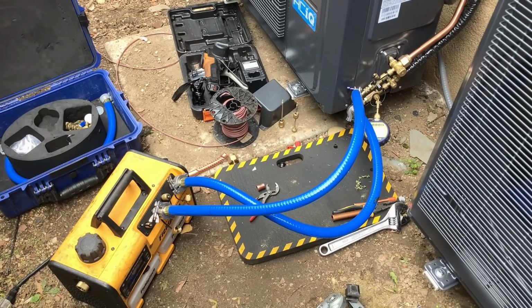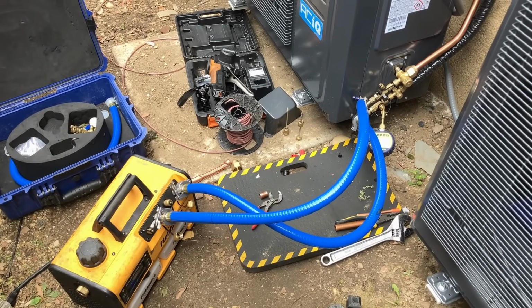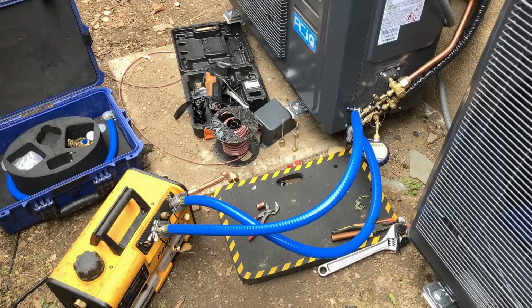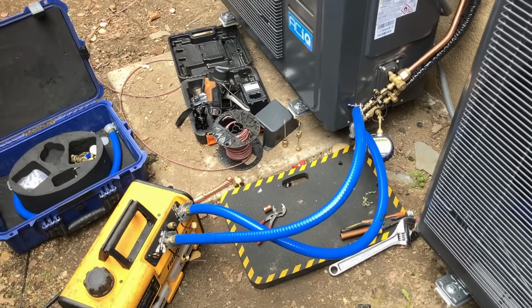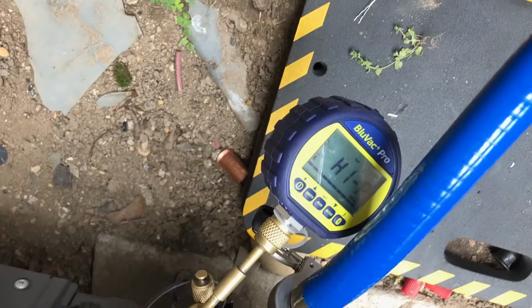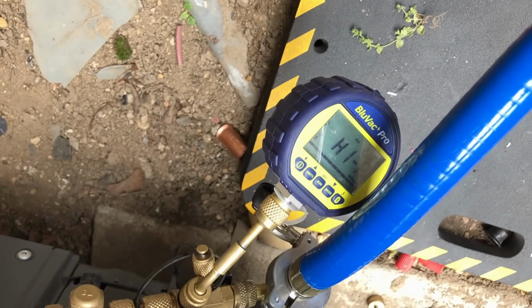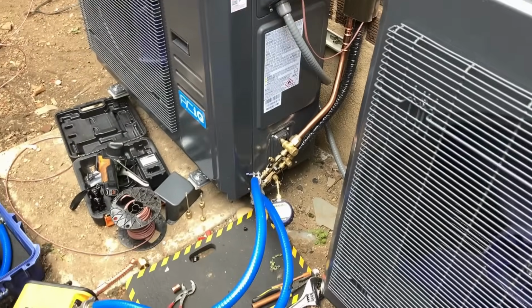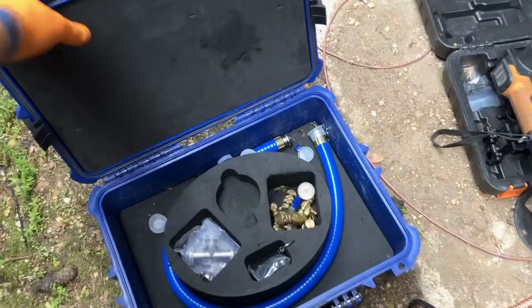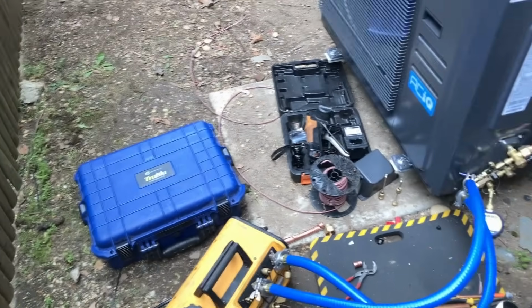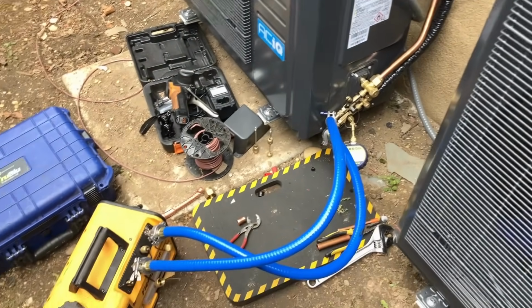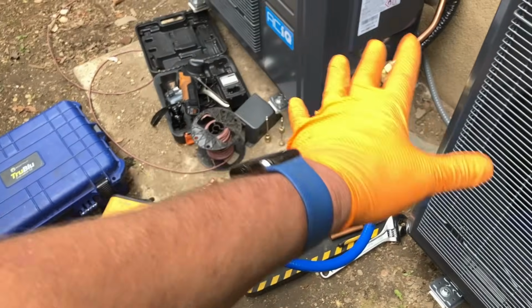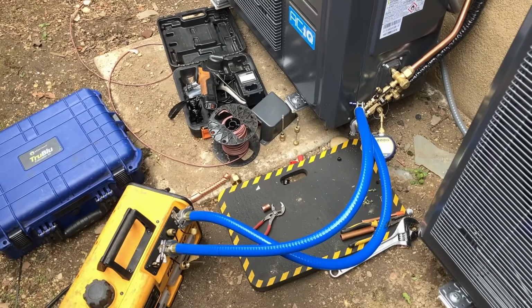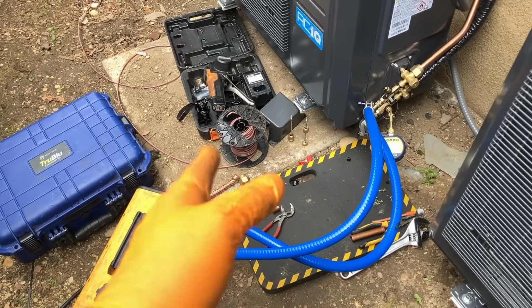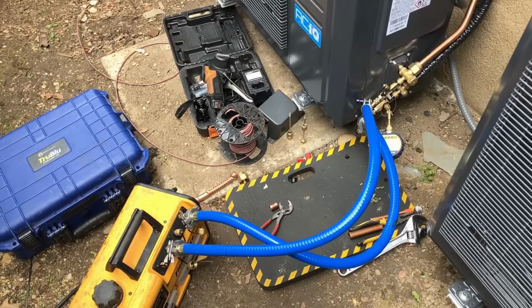All right, I am all set up to vacuum down as deep as we can go. I want this to be a very, very deep and extremely dry vacuum process. I got the TruBlu Vac Plus Pro micron gauge on my liquid side, or high pressure side, in cooling mode. I have the AccuTools True Blue evacuation kit, with both hoses hooked up to my Fieldpiece. Links to all this stuff will be in the description box down below. I should be able to pull a vacuum and pass a decay test in under 10 minutes.